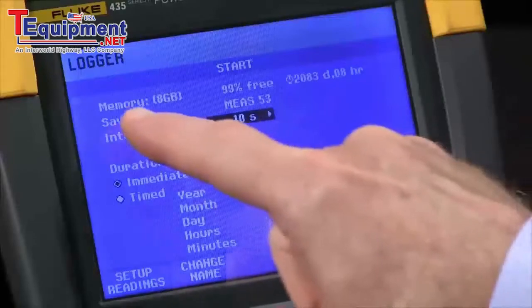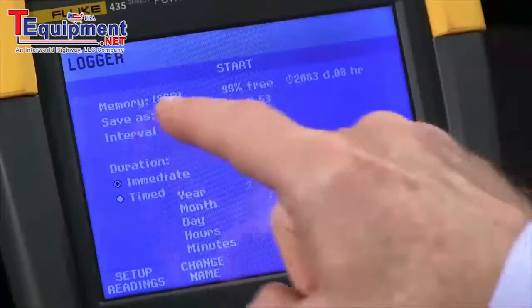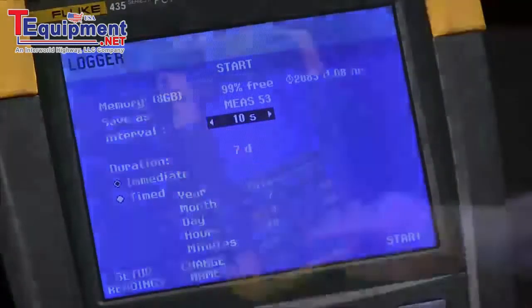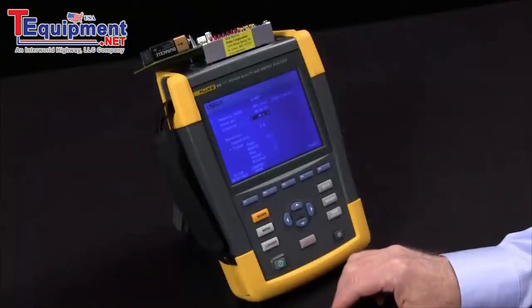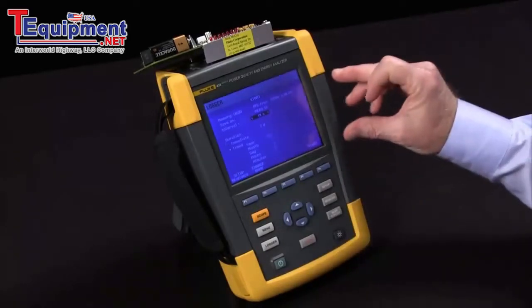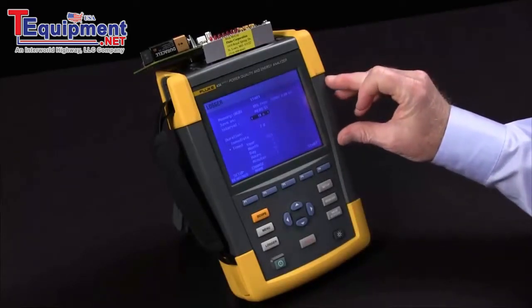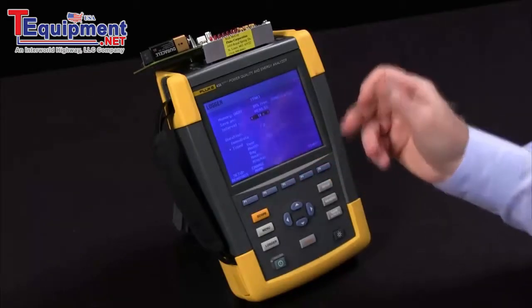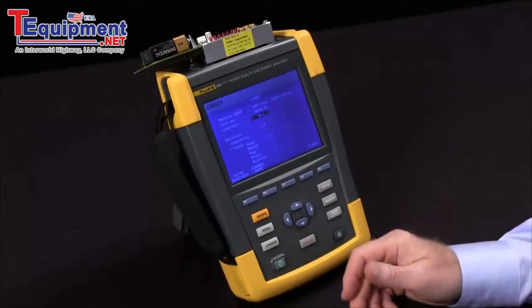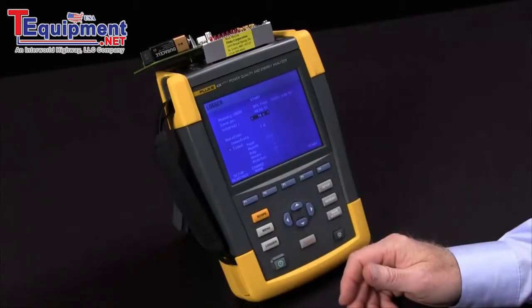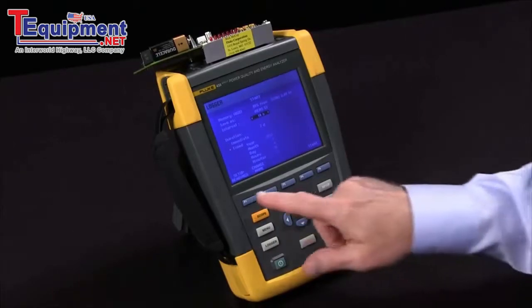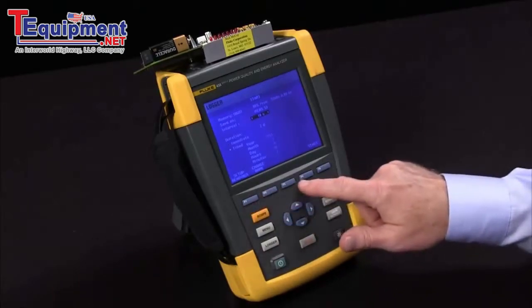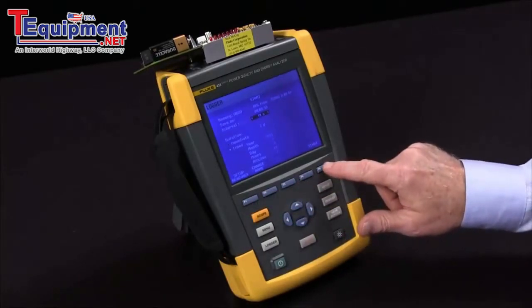At the factory default of 10 seconds, I could record for 2083 days. The key here is that's an 8-gigabyte file, which is really bigger than you want. So if we reduce the number of parameters we record and keep the averaging time at 10 seconds or longer, that allows us to have more manageable file sizes.